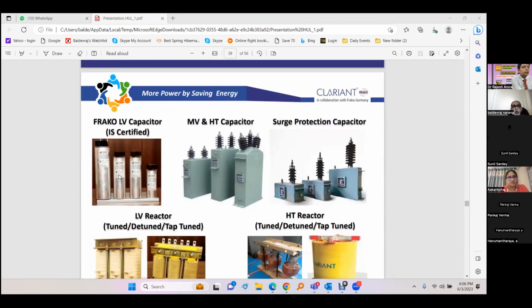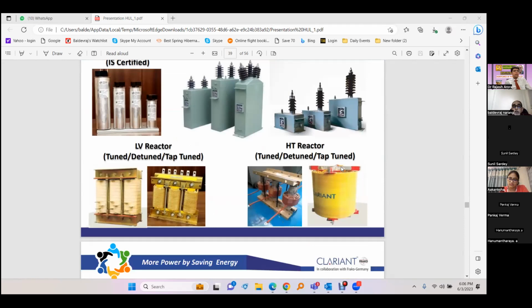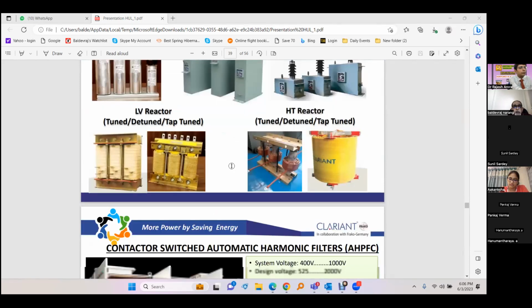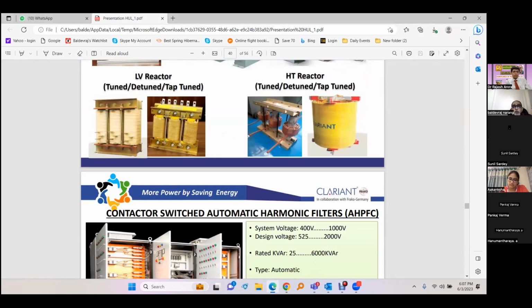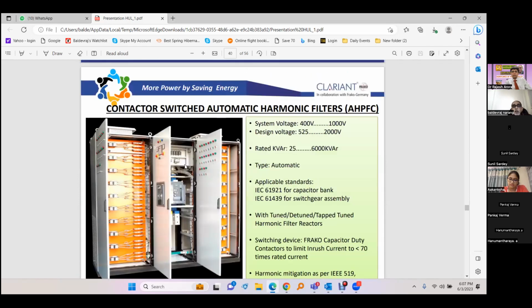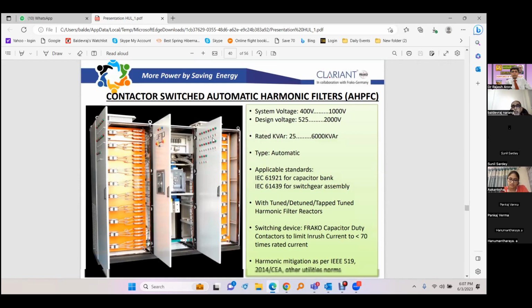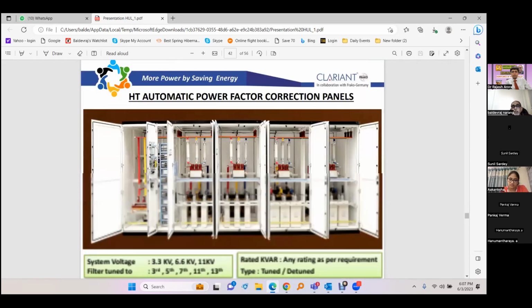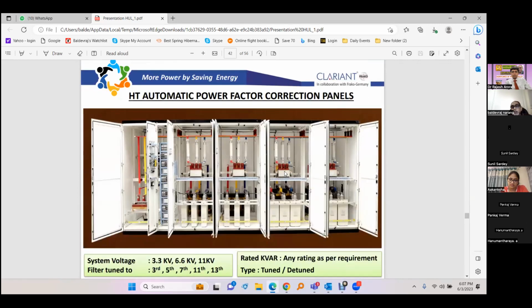So this is how the equipment looks. These are capacitors which we import from Frako, Germany. Then we have our own Indian capacitors also, MV and HT. We have Indian manufacturing as well as imports. And surge protection is there. These are the reactors, LV and HV both. This is a contactor switched APFC panel, and this is a thyristor switched panel. And now we also have medium voltage switched capacitor banks. We use vacuum contactors up to 33 kV, and we have the APFCs available.